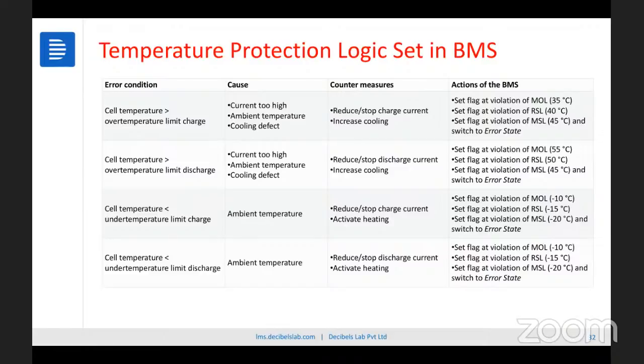How do we actually protect a cell from temperature? We have cell temperature greater than over-temperature limits. The reasons possibly are like you're trying to draw a lot of current, or the ambient temperature itself has gone high, or the cooling system is faulty. So what we do is reduce or stop the charge current, or increase the cooling. This state is only when the cell is getting charged. When the cell temperature goes higher than the over-temperature limit during discharge, it means you're drawing too much current, ambient temperatures are too high, or maybe the cooling is defective. Reduce or stop the discharge current, or increase the cooling systems. So like this, we define specific error states and what to do and what not to do in each case.